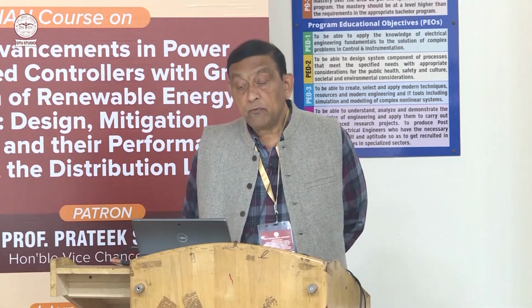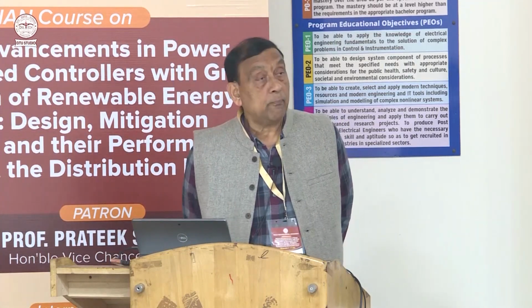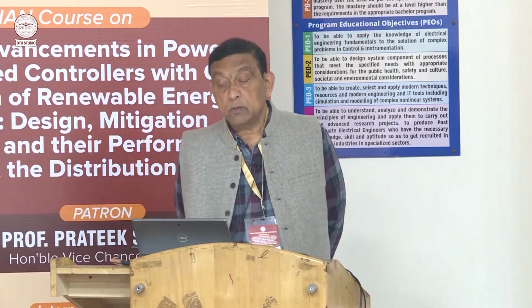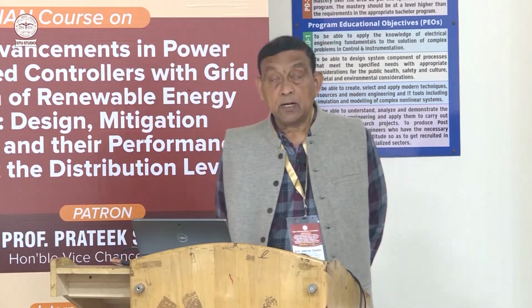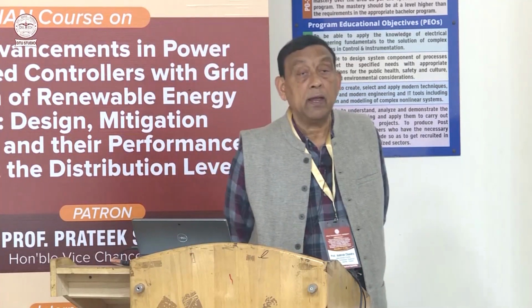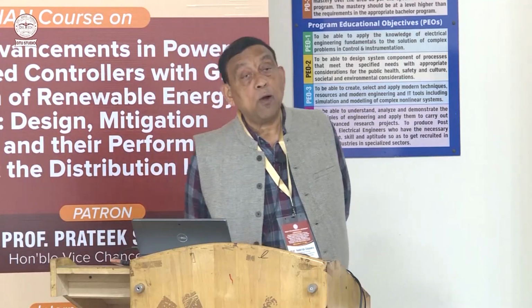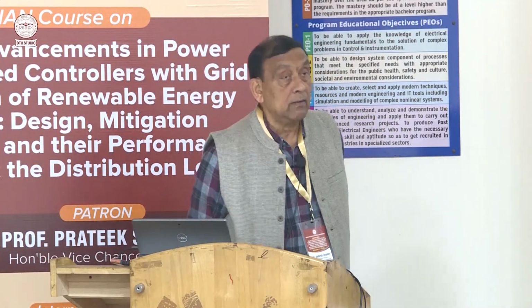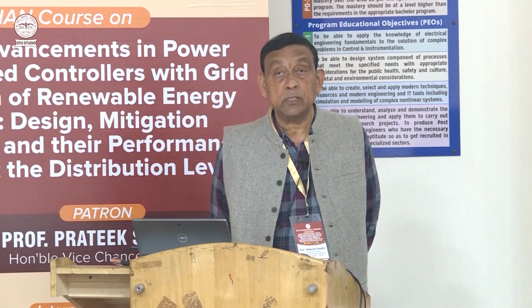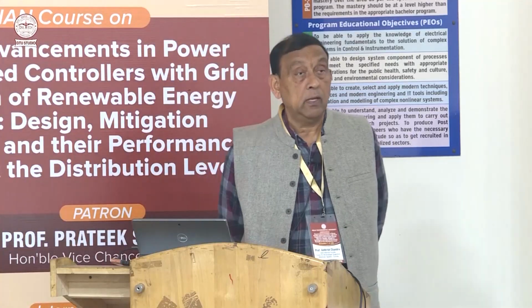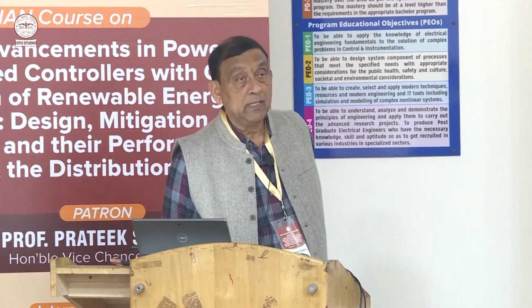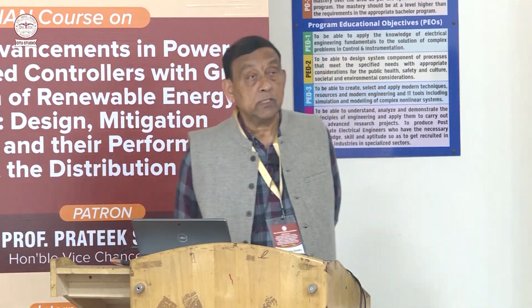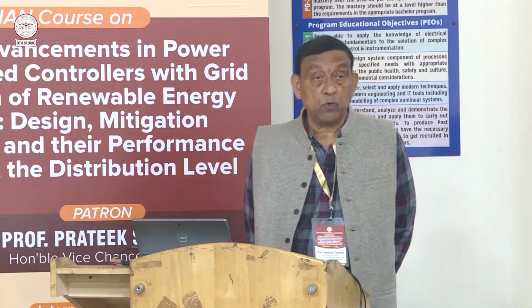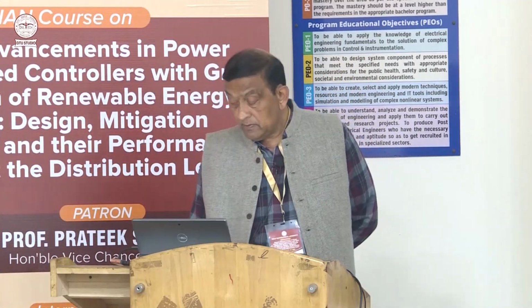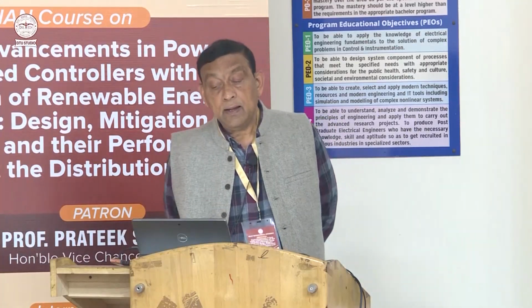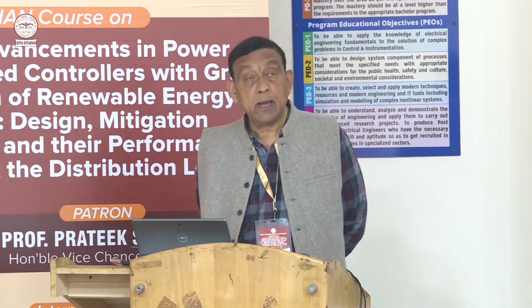Then we talked about what problems harmonics cause: increased losses in conductors, for reasons such as skin effect and ohmic losses, and ferromagnetic losses like hysteresis losses and eddy current losses. These are very important issues. If we have harmonics, high frequency is present, so hysteresis losses are proportional to the frequency, while eddy current losses are proportional to the square of the frequency. We will perhaps see this a little again.